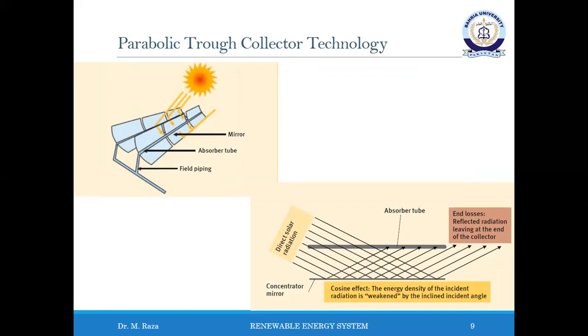During the course of the day, the sun moves southward and its light falls at an increasingly oblique angle on the collector. The sun rays continue to focus through the tracking parabolic aperture onto the absorber tube but are reflected back across a longer distance. The inclined incident sunlight causes the radiation energy captured per unit area to be correspondingly reduced relative to the cosine of the incident angle.